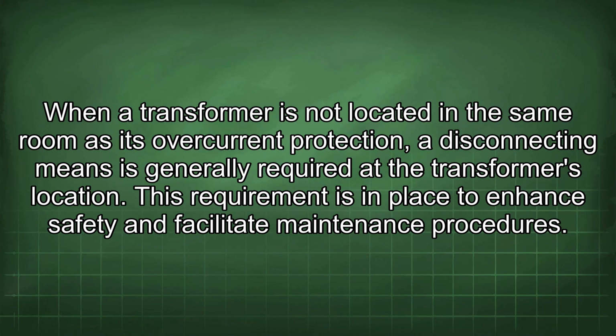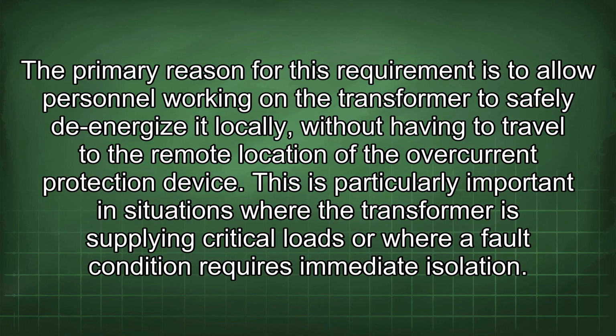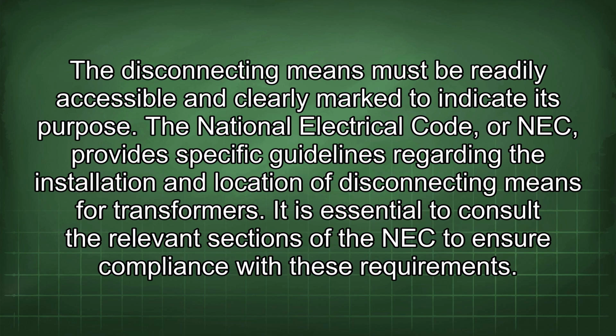When a transformer is not located in the same room as its overcurrent protection, a disconnecting means is generally required at the transformer's location. This requirement is in place to enhance safety and facilitate maintenance procedures. The primary reason for this requirement is to allow personnel working on the transformer to safely de-energize it locally without having to travel to the remote location of the overcurrent protection device. This is particularly important in situations where the transformer is supplying critical loads or where a fault condition requires immediate isolation. The disconnecting means must be readily accessible and clearly marked to indicate its purpose.